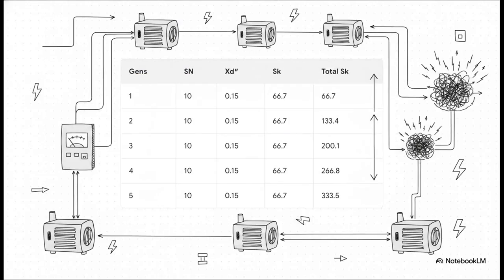Let's ground this in a real-world example so you can actually visually anchor how aggressively this fault power stacks up. Here we have identical generators, each rated for 10 megavolt amperes with a subtransient reactance of 0.15. Watch the running total of our short circuit power, Sk. With just one generator, the fault current is highly manageable, right? But add a second, and it doubles. Add a third, a fourth, and you can see the total Sk absolutely rocketing upward.